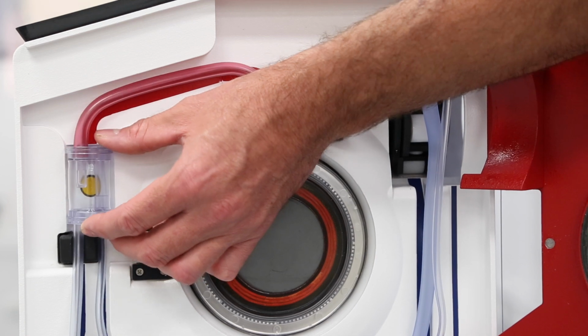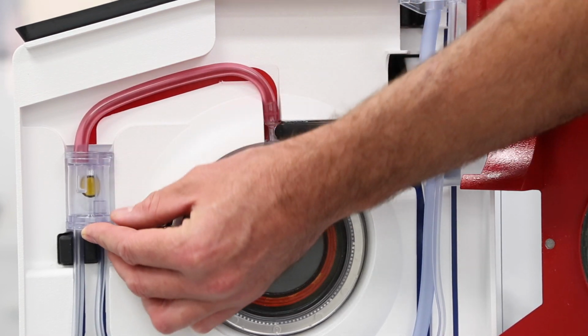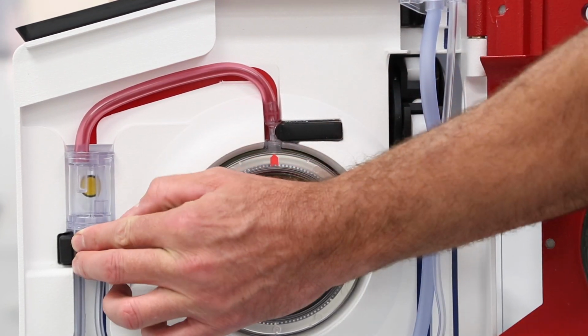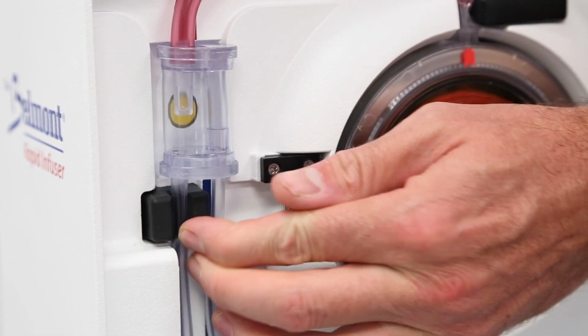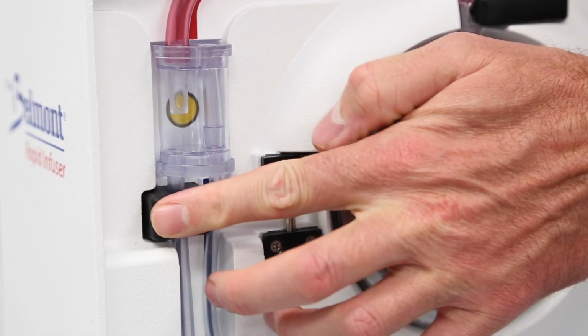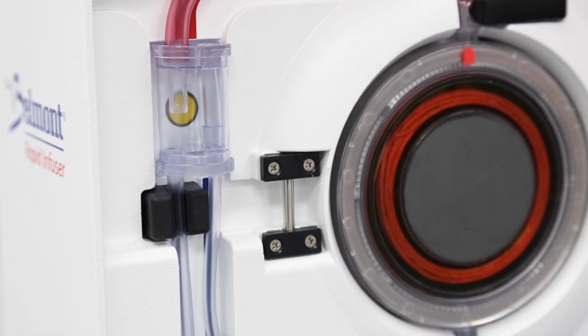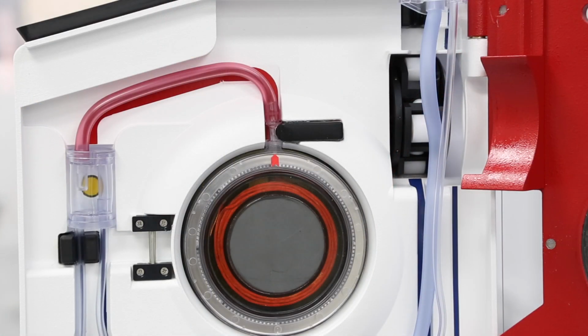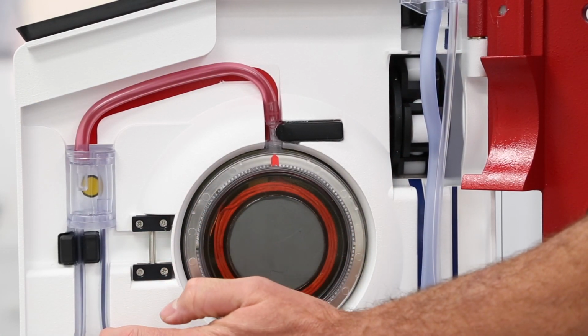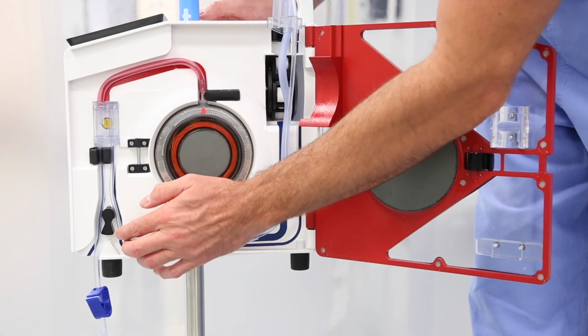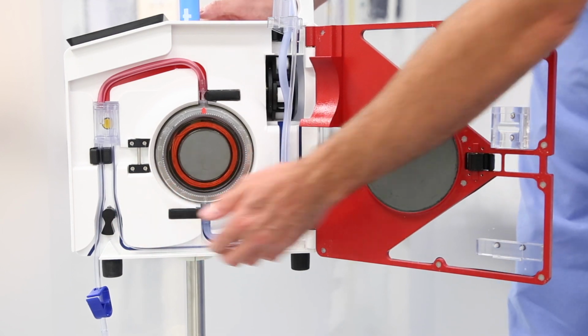Align the red tubing on top of the red stripe and place the pressure chamber into the pressure channel. Press the infuse line into the secondary air detector to the left of the patient safety valve wand. Note, the infuse line should be at or below flush within the air detector. Place the thinner recirculation line to the right of the air detector and to the right of the valve wand.